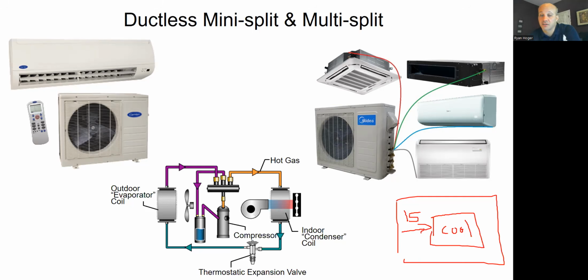Because if this guy's sitting here in the middle, the zones next to him, it's 72 degrees here, 72, 72, 72, 72 on the floor above, 72 on the floor below. All 6 sides of that middle box, it's 72. That zone thinks it's sitting in San Diego. It has no idea it's in International Falls, Minnesota or whatever, or the upper coastline of Maine. It doesn't know.